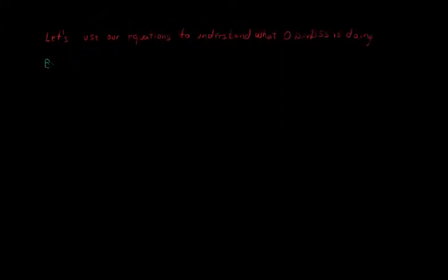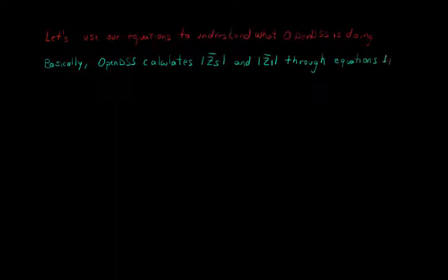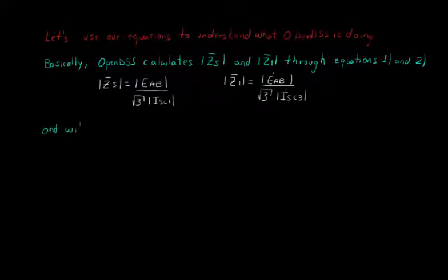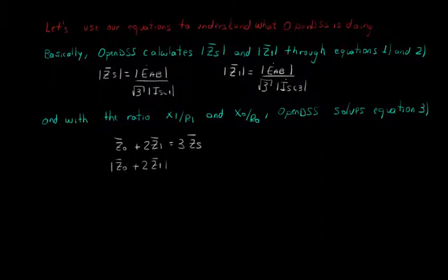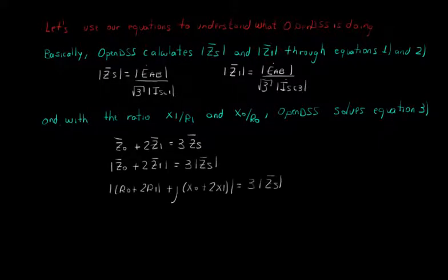Basically, what OpenDSS does is to calculate the module of ZS and the module of Z1 through equations 1 and 2, from which we can get that the module of ZS is equal to the module of EAB over square root of 3 times the module of ISC1, and the module of Z1 is equal to the module of EAB over square root of 3 times the module of ISC3. Finally, with the ratios X1 over R1 and X0 over R0, OpenDSS takes the module of both sides of equation 3 and solves for R0. With R0, X0 is also defined due to the ratio X0R0.